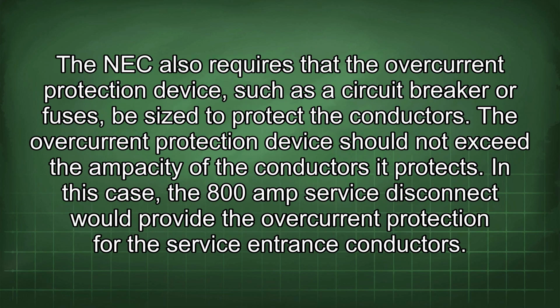The NEC also requires that the overcurrent protection device, such as the circuit breaker or fuses, be sized to protect the conductors. The overcurrent protection device should not exceed the ampacity of the conductors it protects. In this case, the 800 amp service disconnect would provide the overcurrent protection for the service entrance conductors.